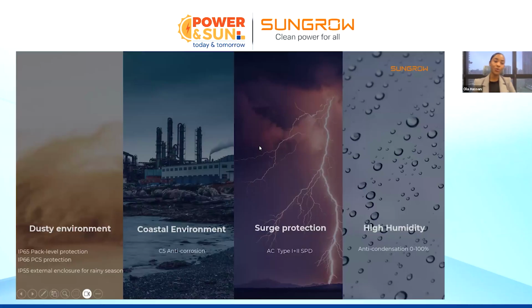So the system is also IP65 level protected on the overall pack level, and IP66 rated protection for the PCS, the power conversion unit itself, and another IP55 rated enclosure for the outer case for the rainy seasons. The system is C5 rated when it comes to anti-corrosion protection, so it can be installed in offshore areas. And also it has surge protection.